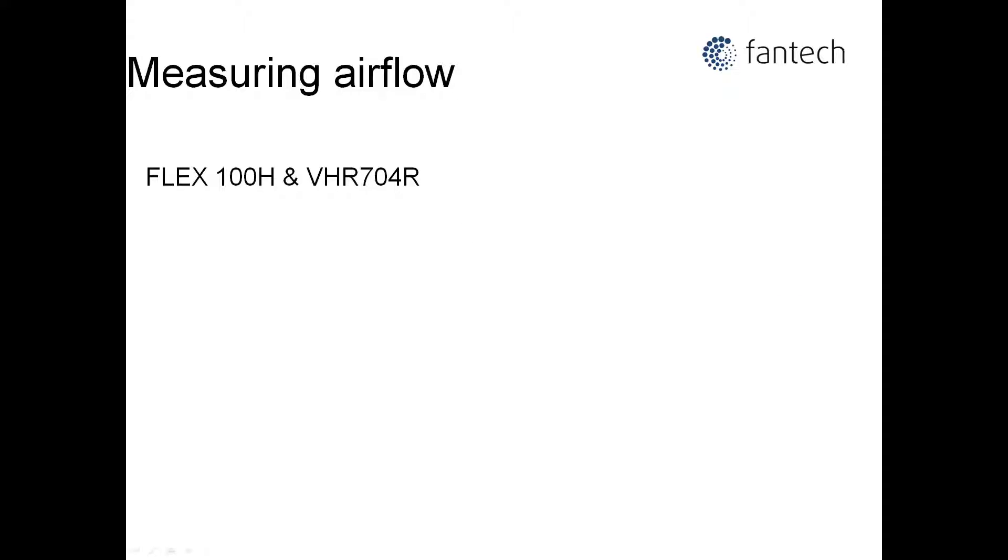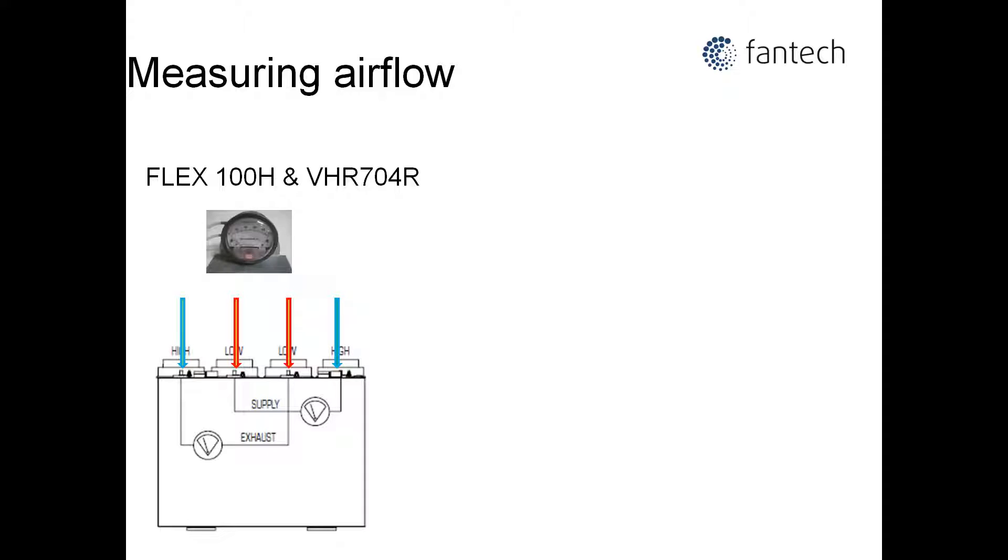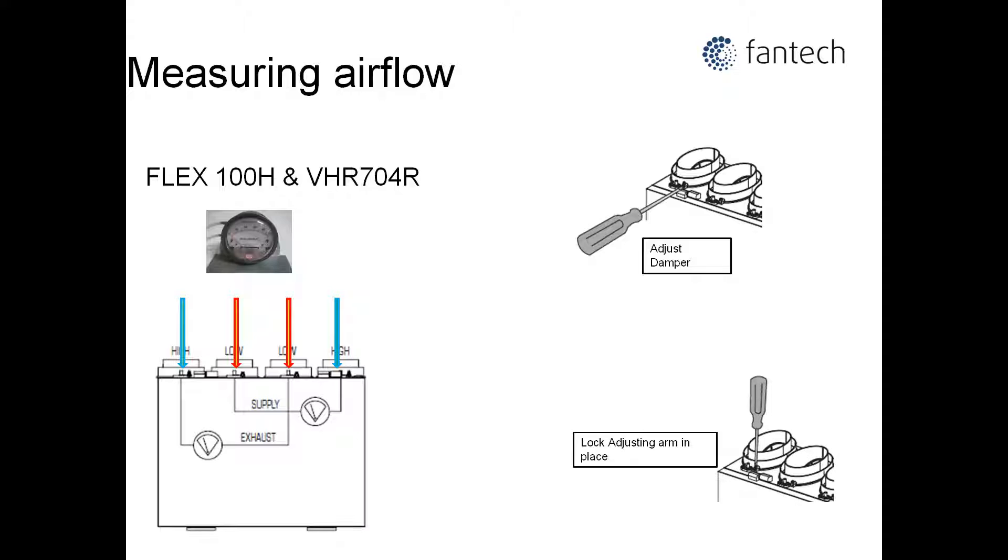A professional would know where and how to use these instruments to take airflow measurements. However, with the Fantech Flex 100H and the VHR 704R, all that is required is a Magnehelic gauge, as the units have integrated pressure ports and balancing dampers. These dampers are easy to adjust and lock. Let's see how balancing is done in practice.